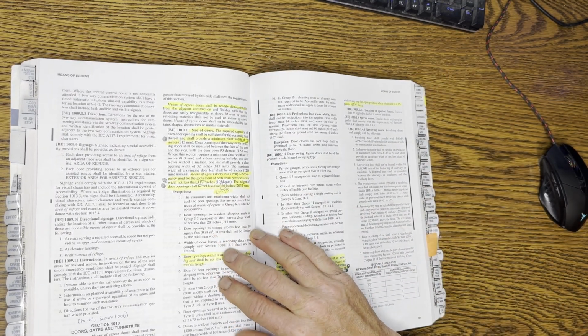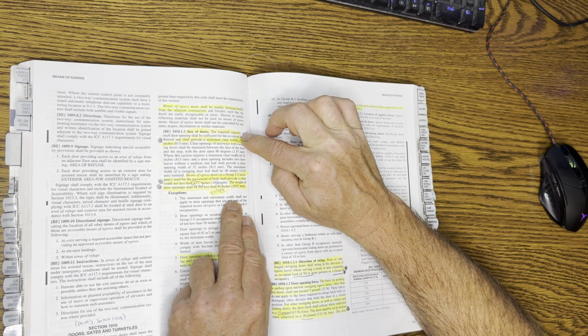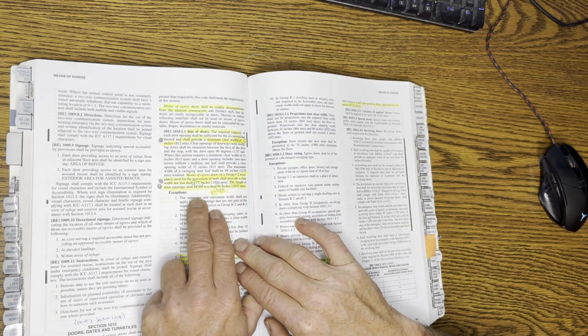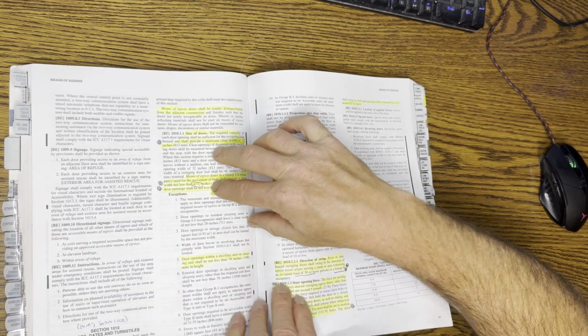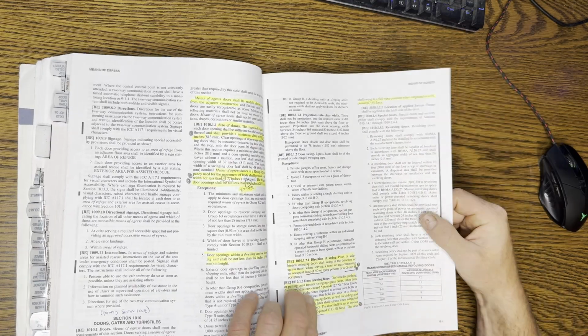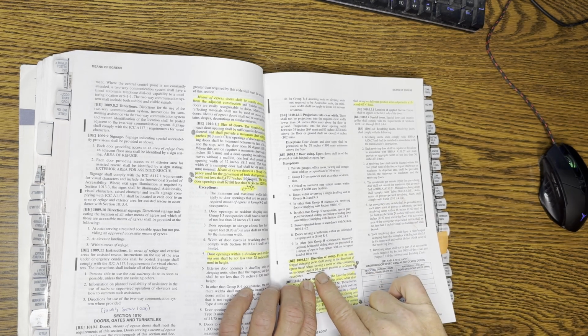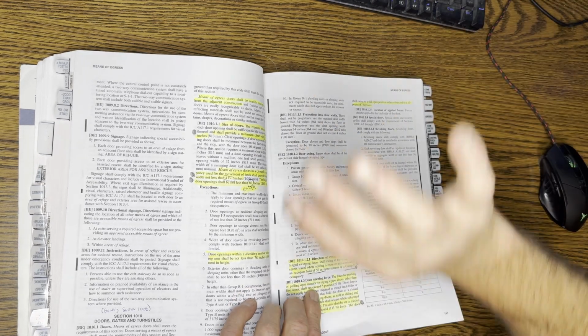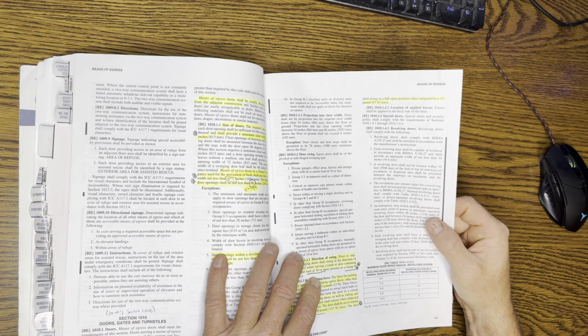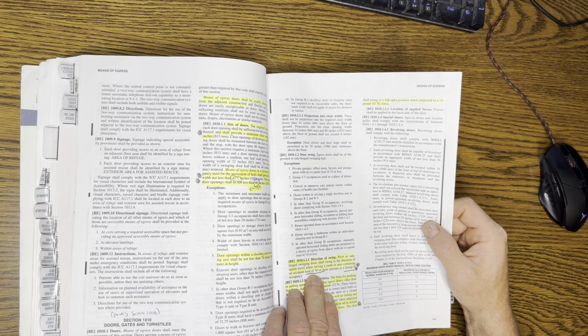Okay, doors, gates, and turnstiles. Let's run through this. Size of doors, it's 32 inches is the minimum. There's some differences. If you're in a hospital, you have to be 41.5 inches, and the height has to be 80 inches. There's some exceptions here. Just read through those. Direction of swing, so in the event of panic and evacuation, if you have more than 49 people, so 50 or more people, the door has to swing in the direction of travel, or if it's a high hazard occupancy. So just keep that in mind. Number is 49, over 49 people. These are also test questions here. Okay, so the 50-person door swing is a question from the test.